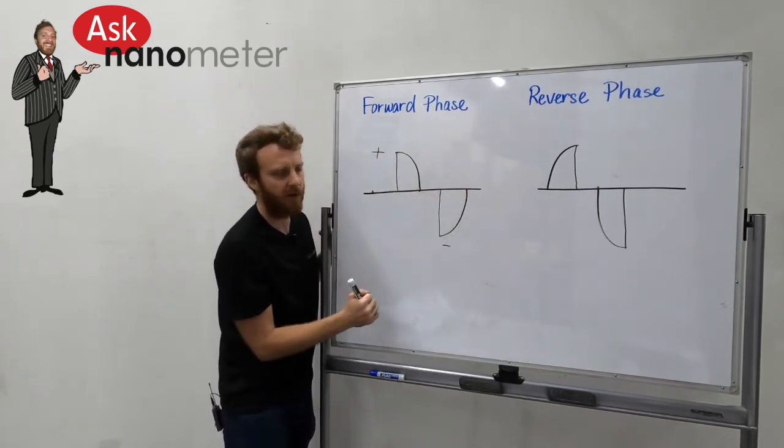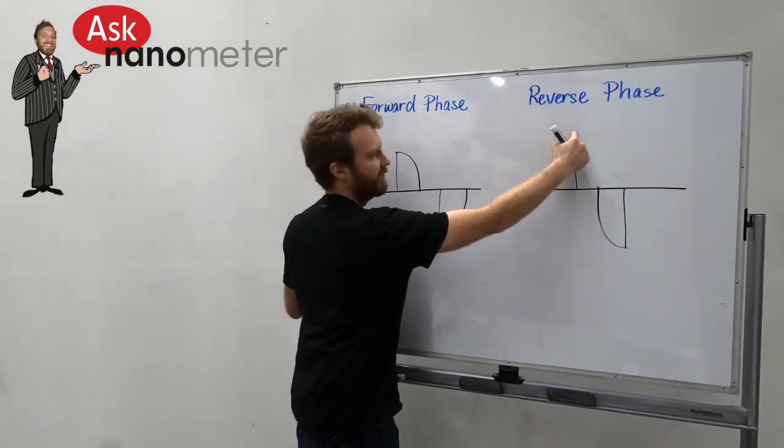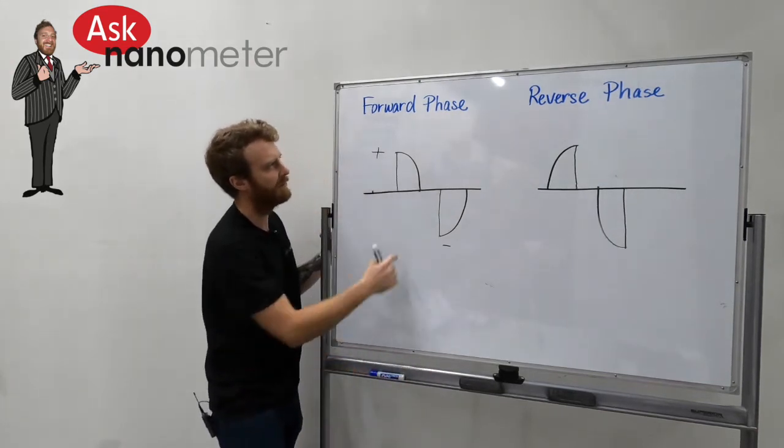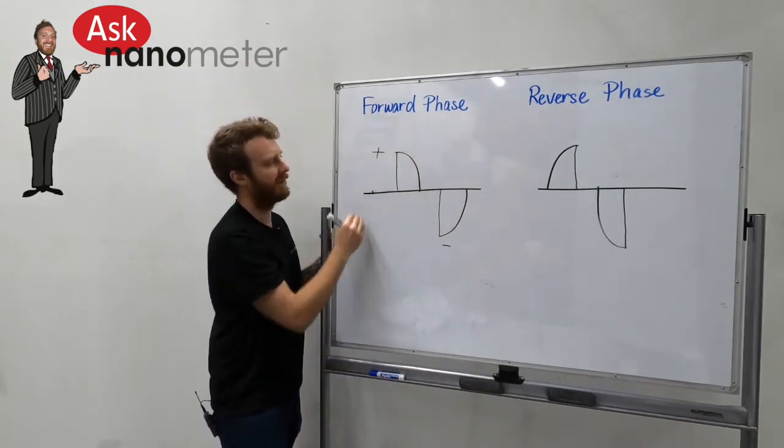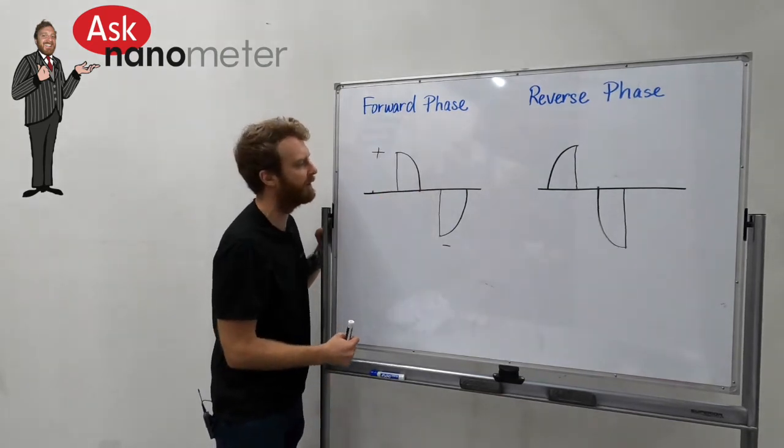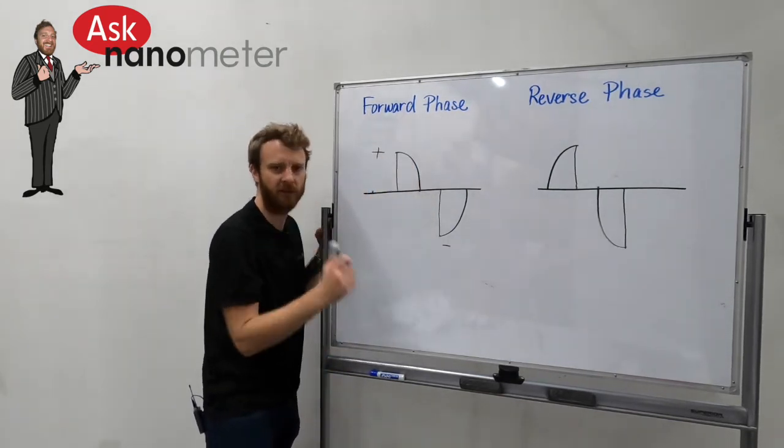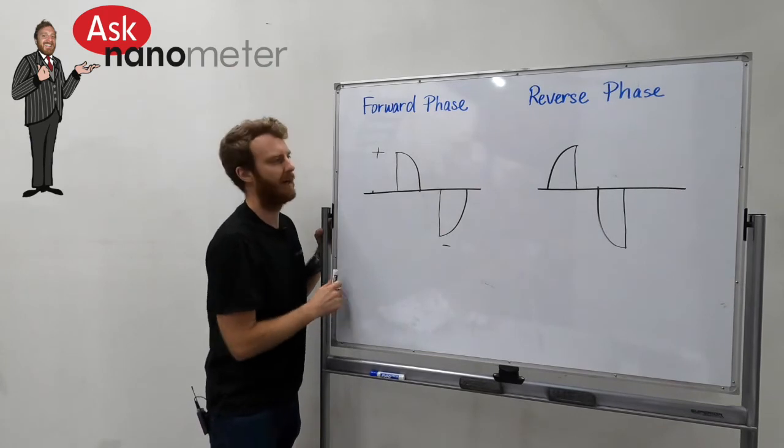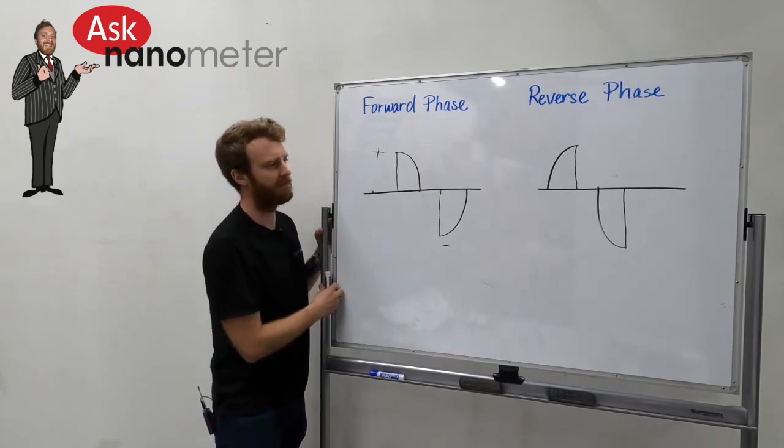The forward phase dimmer is hacking that off and so we have this inrush of maximum current and that over time is just going to kill the driver and make it fail a lot earlier.